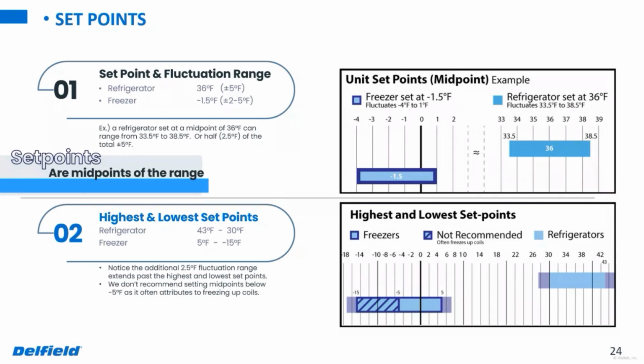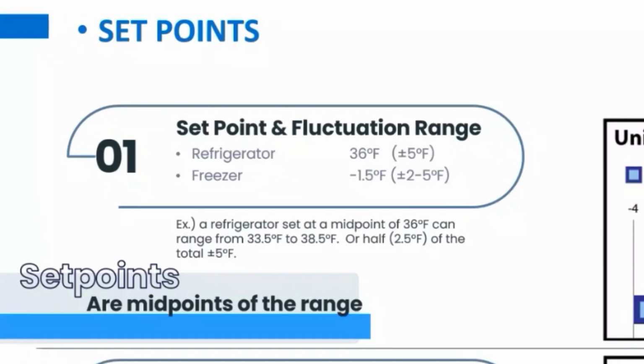So our recommended set point for a refrigerator is going to be around that 36-degree mark. If you're giving me or Bud a call on the phone, we're probably going to tell you 36, maybe 37 degrees. We wouldn't want to dip too much lower than that. When we go 2.5 lower than, say, 35, now we're at about 32.5. We're getting pretty close to running the risk of possibly freezing up some product. So if you stay around 36, 37 degrees, you're typically in a pretty good spot.